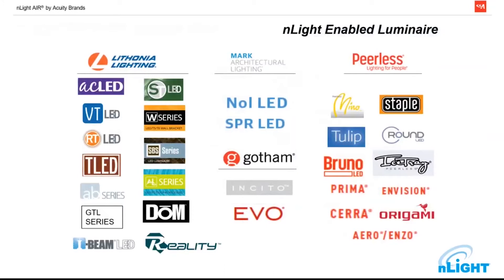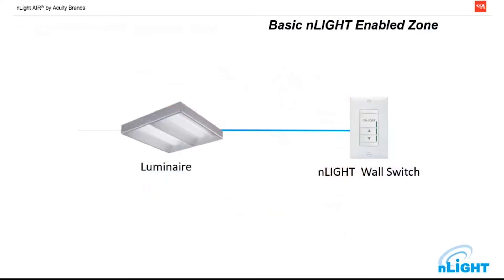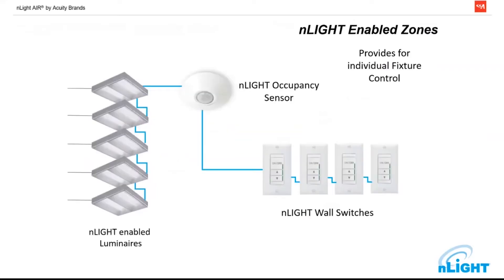Taking a step further is nLight-enabling a fixture, where basically we are integrating all of that control right into the light fixture itself. In a basic nLight-enabled zone, we've removed the power pack. We are bringing power straight to the fixture — no dimming wires, nothing else. Now that fixture is dimmable; it can turn on, off, and dim right from our wall switch. We can add occupancy control, network our fixtures via data chaining on the Cat5, and individually address them. Switch one controls fixtures one and two, switch two controls fixture three, and so on.